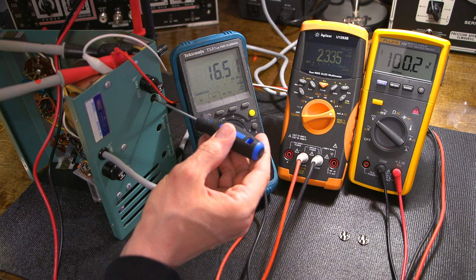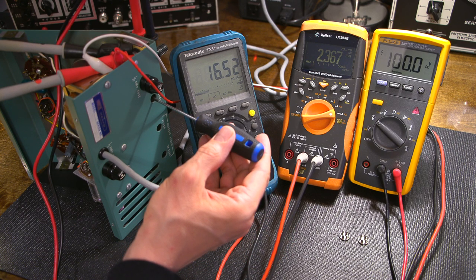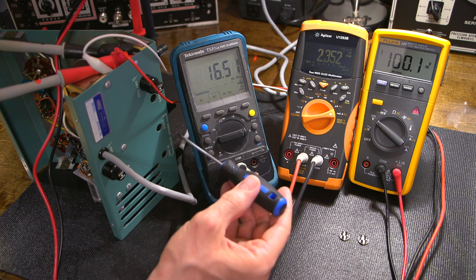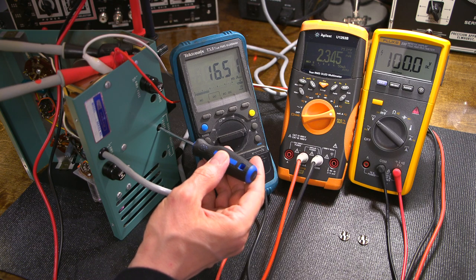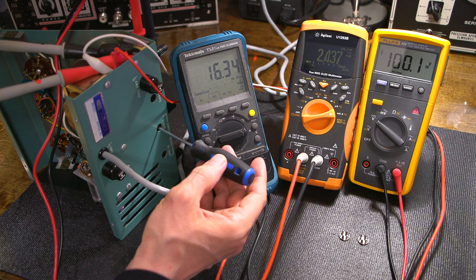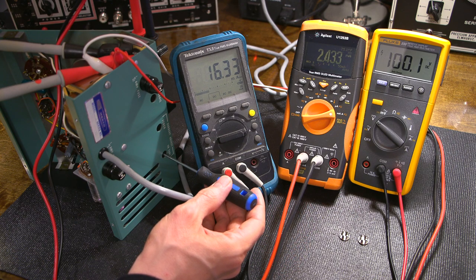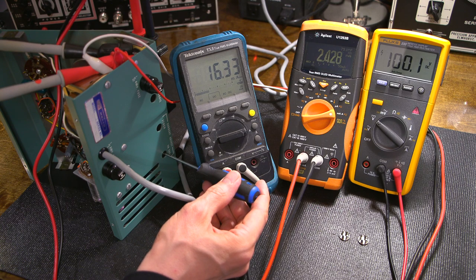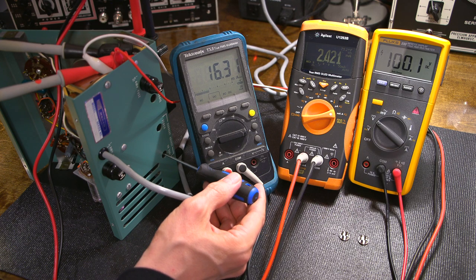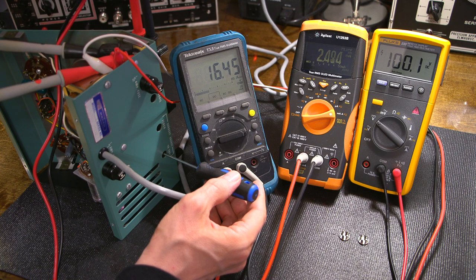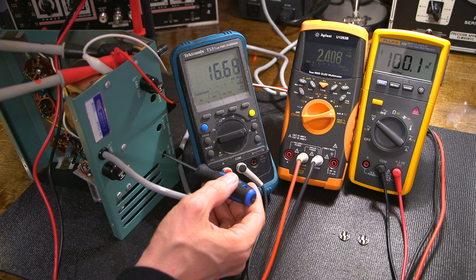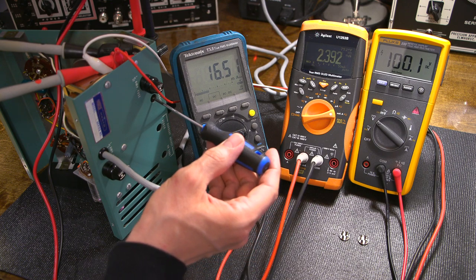Take the calibration, take that back down to 100 volts again. And we're at 2.35, so I could probably bump that up to 2.4. And now that moved that to 16.3. Bump the VR tube back up to about 16.5. Dips in the line voltage here and everything. It's 2.4, right? You can see the line voltage came up here. You can see how that would move it. And then I can just wait for everything to settle back down again.